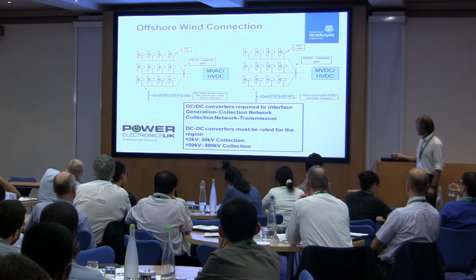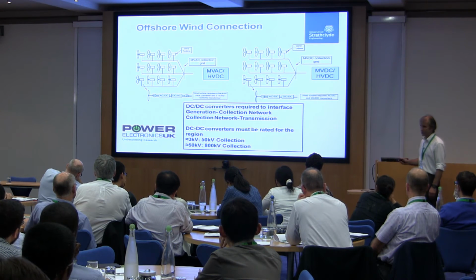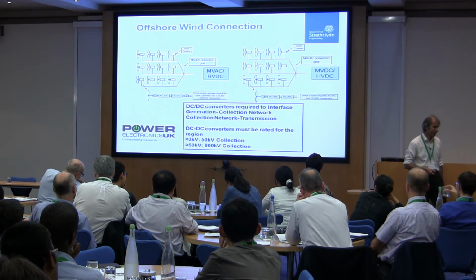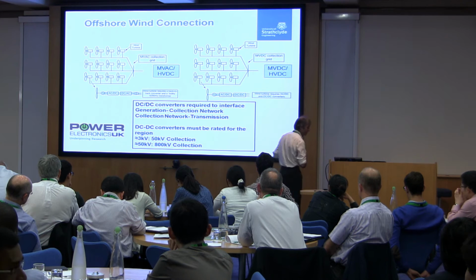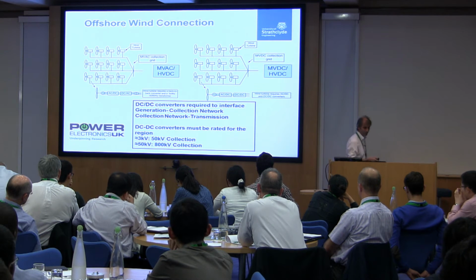Having moved from your collection network, you've probably got a second stage of conversion required to step up from 50 kilovolts to 100 kilovolts. This DC to DC converter, in our black box, just looks like another power conversion stage. But implementing that, and what we can achieve, will really tell us whether this type of approach to large-scale energy collection or energy distribution at the other end is going to be viable.